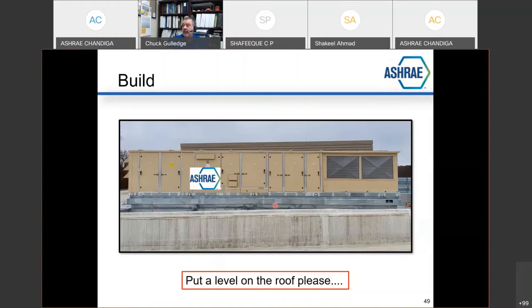They ordered a flat roof curb with no pitch to it, installed the curb, flashed the curb, put the unit on the roof, and then were wondering what to do about all the cooling coil condensate downstream of the evaporator coil that was overflowing the drain pan and falling down in the building. Really, this happened. This really happened.